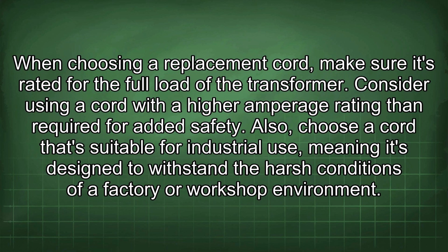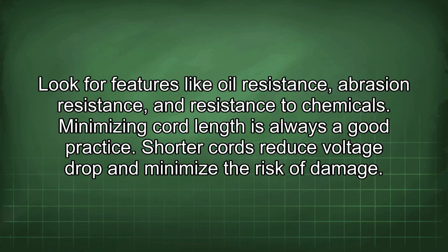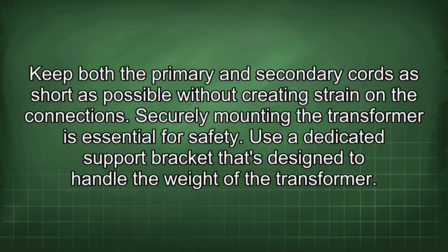Also, choose a cord that's suitable for industrial use, meaning it's designed to withstand the harsh conditions of a factory or workshop environment. Look for features like oil resistance, abrasion resistance, and resistance to chemicals. Minimizing cord length is always a good practice. Shorter cords reduce voltage drop and minimize the risk of damage. Keep both the primary and secondary cords as short as possible without creating strain on the connections.